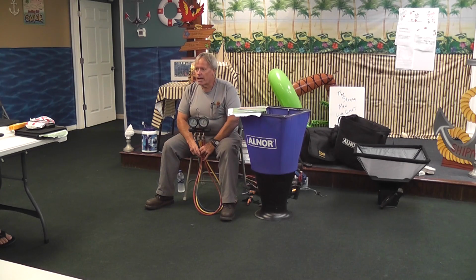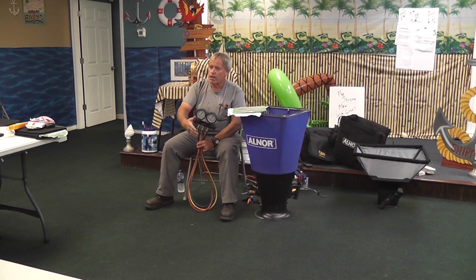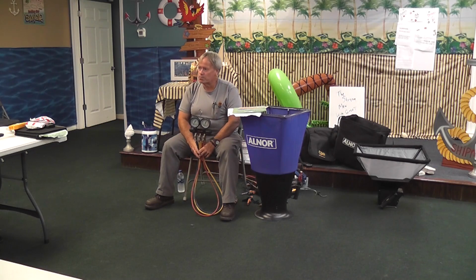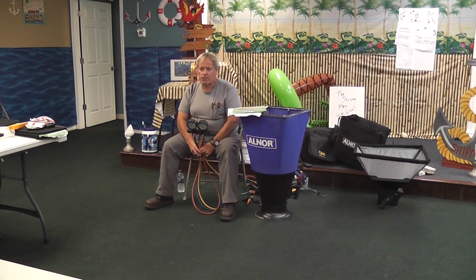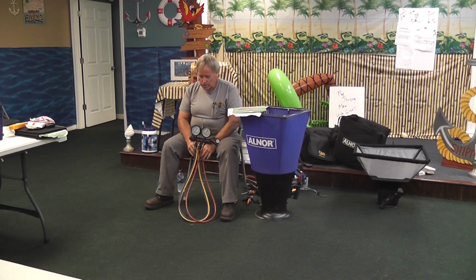Also, if you have a machine that has habitual leaks in it that you can't find over a period of time, 410A is a common air conditioning refrigerant, it will destroy the charge because it lets off a little more of this gas and a little less of this, and you don't have the compound that was meant to be in the first place. You take your gauge off, the valve that's left to hold the refrigerant in is called the Schrader valve. It's the same valve that's in your car tire. It's not meant to hold anything in it for any period of time. It's meant for you to get whatever you have off of it until you put a cap on. A brass cap, not a plastic one. Never tighten the cap, lost charge.